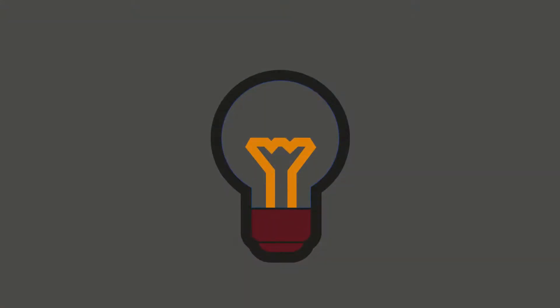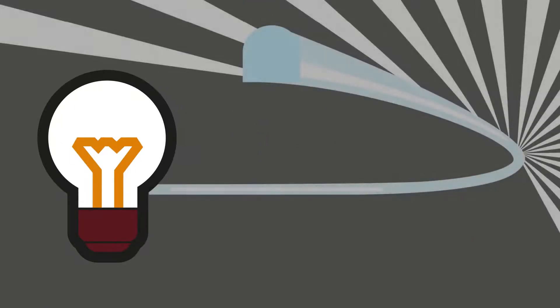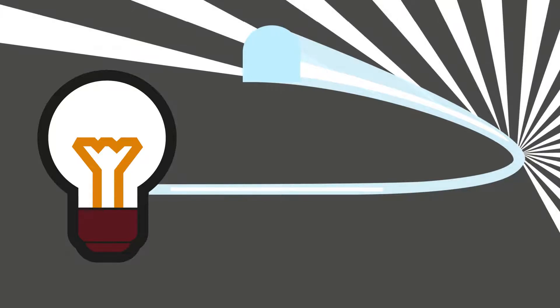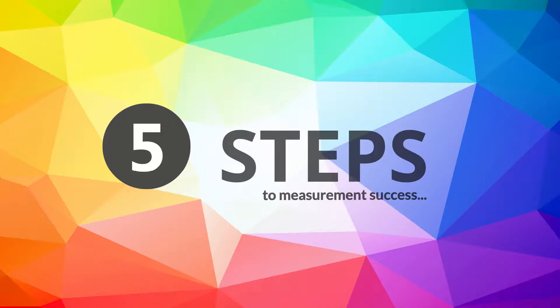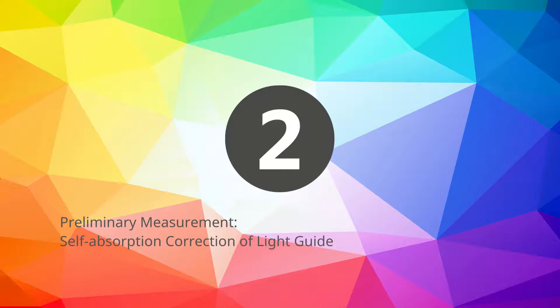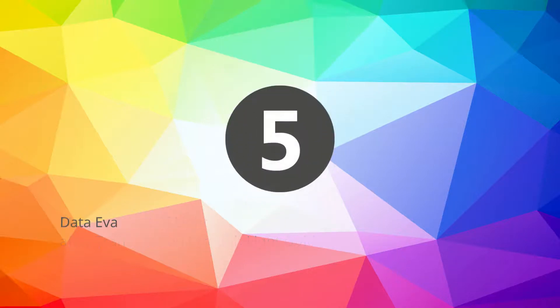The measurement of a light guide's transmission properties consists of two measurements. First, the light is measured which the light source sends through the light guide — typically LED-based light sources are used for this purpose. In the second measurement, the light is measured when exiting the light guide. Comparing these two measurements gives information about the color shift during transmission. A series of five steps needs to be conducted: preliminary measurement and self-absorption correction of the LED light source; preliminary measurement and self-absorption correction of the light guide; measurement of light emitted by LED; measurement of light after transmission through the light guide; and data evaluation.